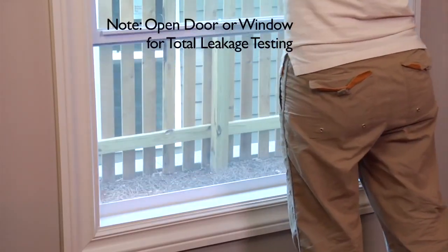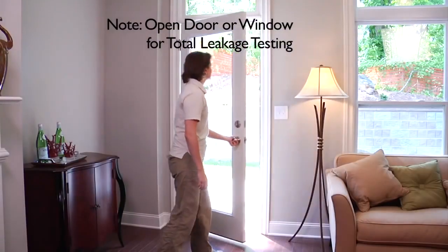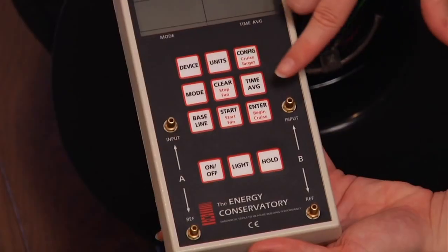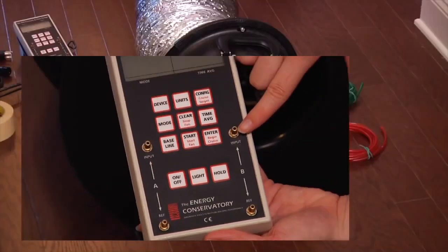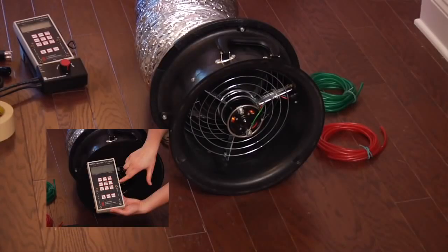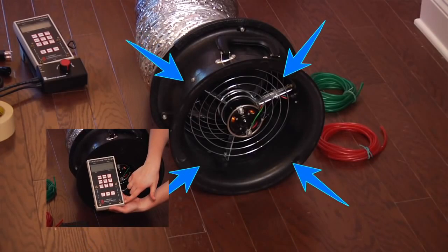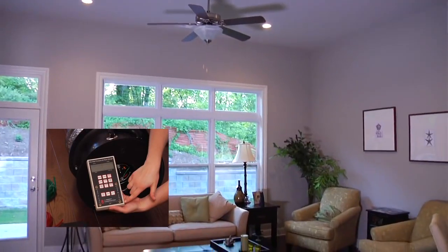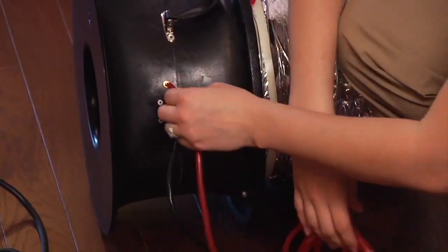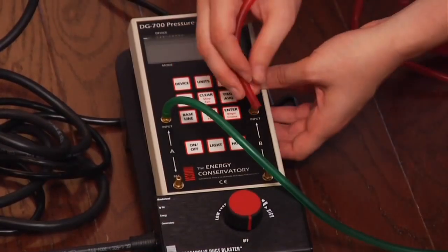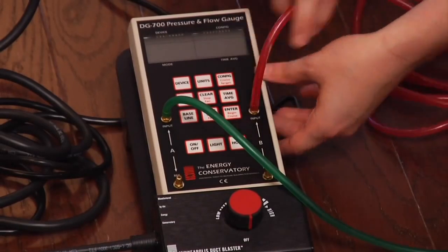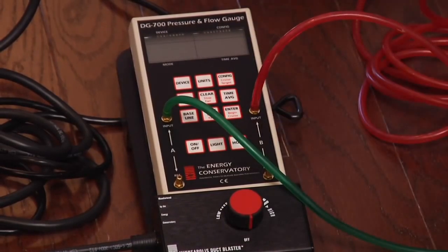Open a window or door and the pressure of the house will be equal to the outside. The B side of the gauge will measure the pressure difference across the fan with reference to the fan inlet side, in this case, the house. Connect a red tube from the fan to the upper input tap of side B of the gauge. The lower reference tap needs to remain open to the house.